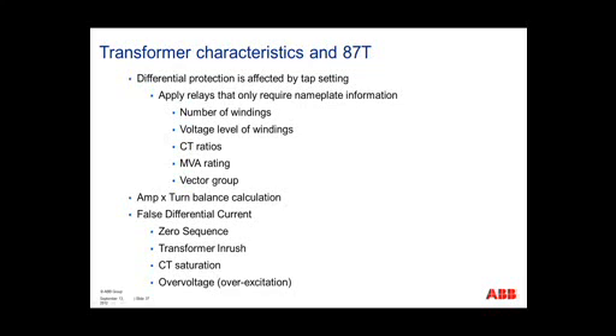Now we need to look at what causes a false differential current. Different sources of false differential current could be from zero sequence, from transformer inrush, from CT saturation, or from overvoltage or overexcitation. And these are the four things we're going to look at and how to account for them in our differential protection.